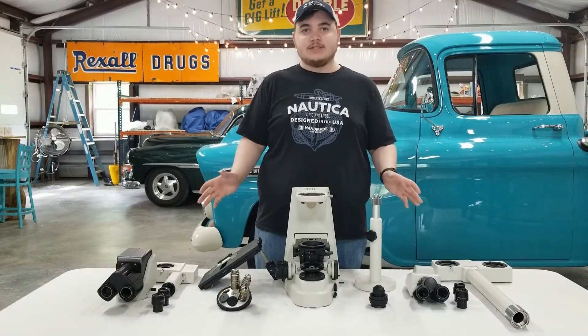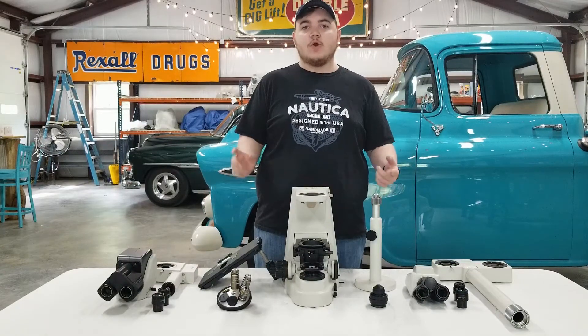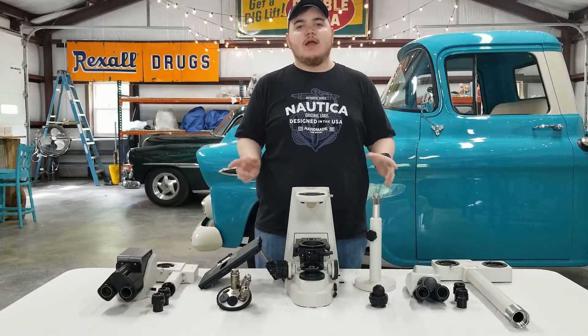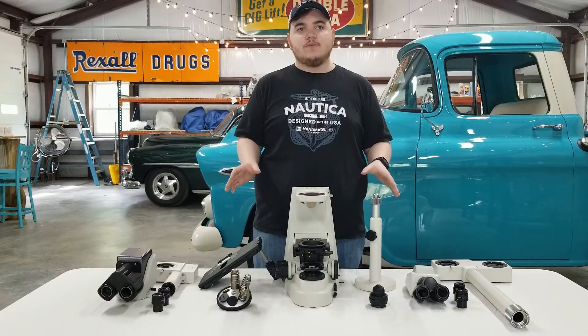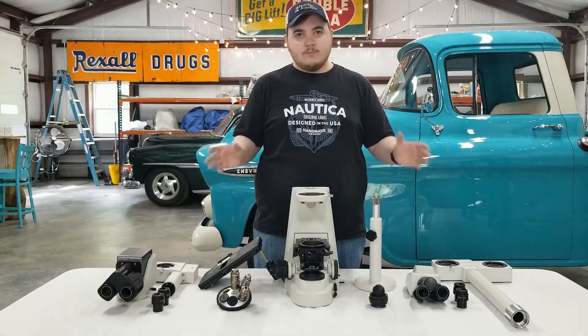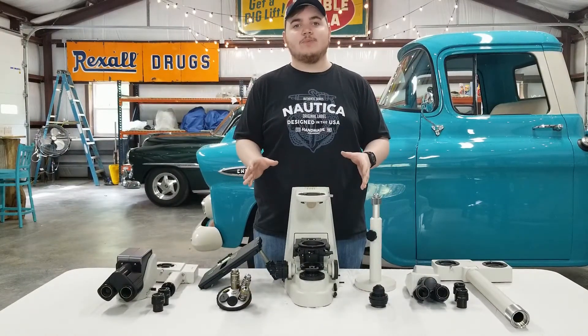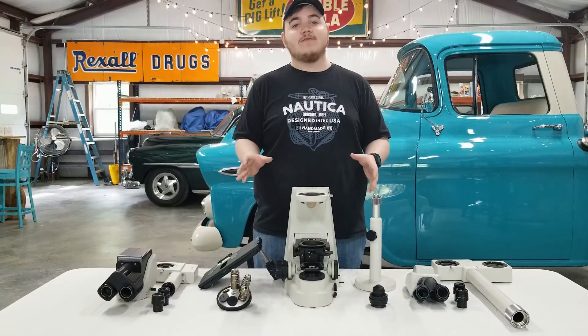So that is the steps on how to disassemble a multi-headed Nikon. If you're interested in how to reassemble it, just go ahead and play this video in reverse. As far as packing is concerned, we do have a video on how to pack an Olympus BX41 — however, the principles are just the same as if you were packing any microscope. Double box everything, wrap everything in bubble wrap, and pack it well and secure so it doesn't move during shipping. Thank you for watching, and have a nice day.